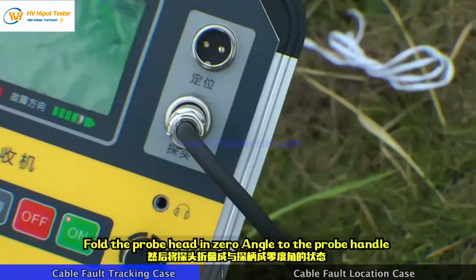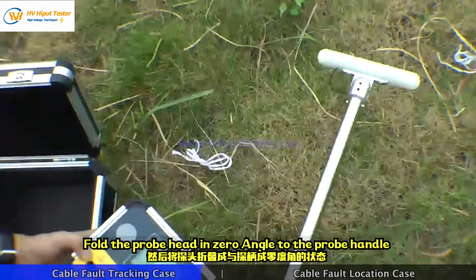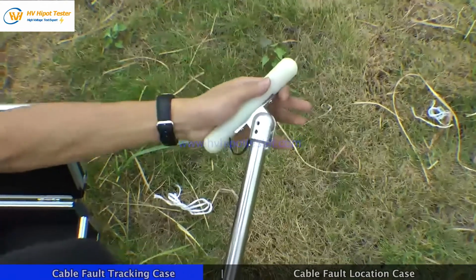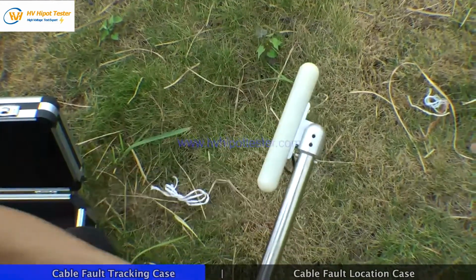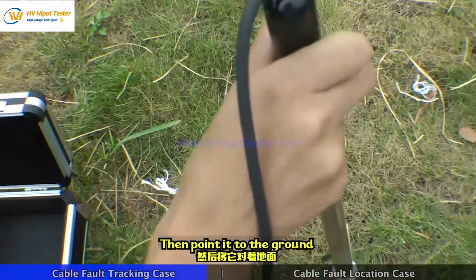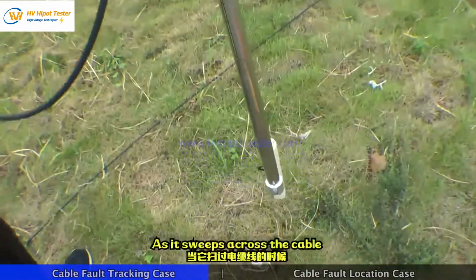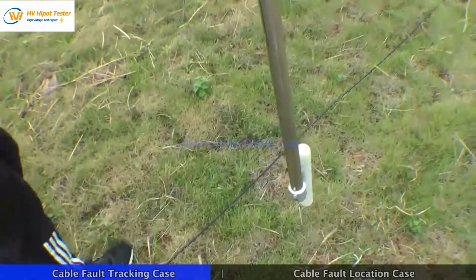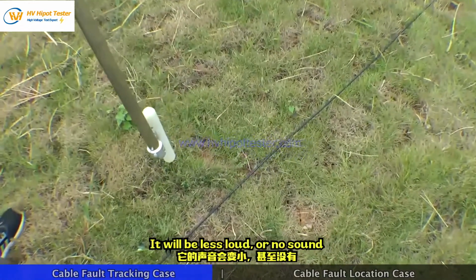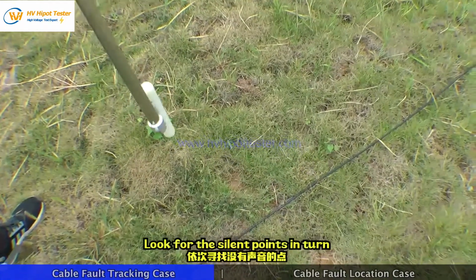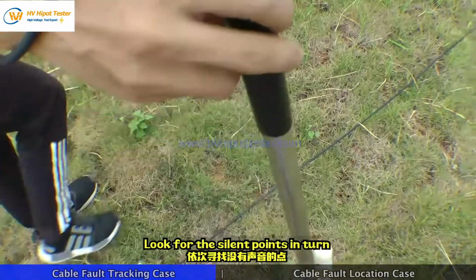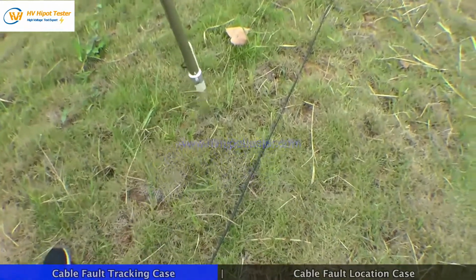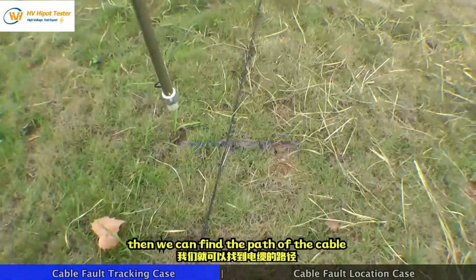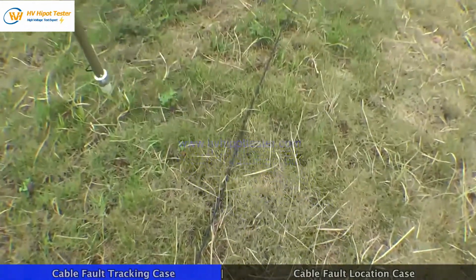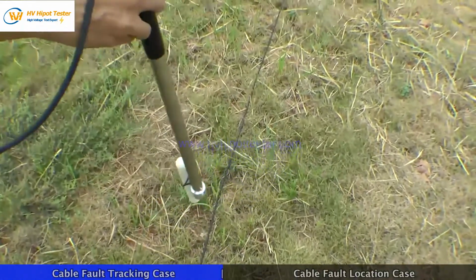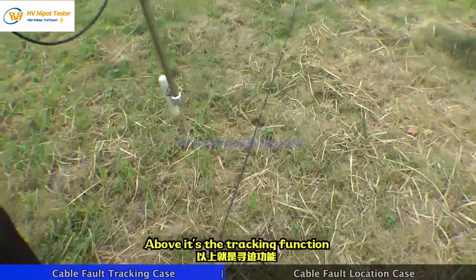Fold the probe head at 0 angle to the probe handle, then point it to the ground. As it sweeps across the cable, it will be less loud or no sound. Look for silent points in turn. Then we can find the path of the cable. Above is the tracking function.